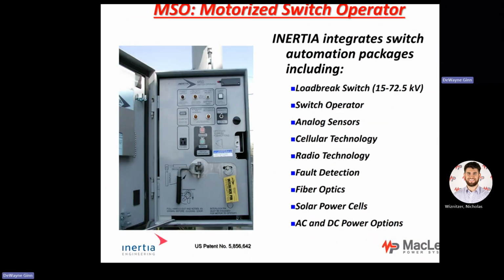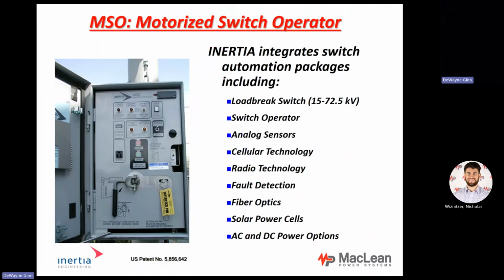And when I open it up, I have to lift them up. The decoupler, that's how I decouple the switch, down to the left here. I pull it up and I decouple the switch. The interlock pin, I pull it out, and I de-energize the motor operator. There's a manual handle, I can operate it manually in the back as well. So that's kind of the internal of a motor operator.